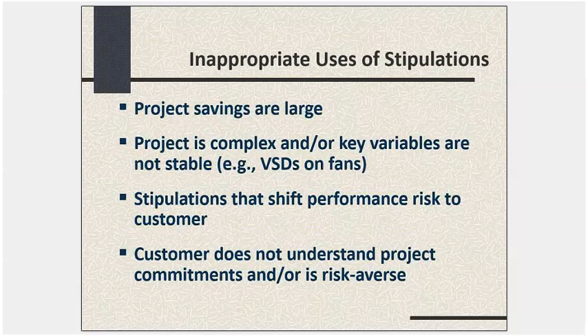Now, when may it not be a good time to use stipulations as opposed to measurements? When the project savings are really big, very valuable. When the project is really complicated, with a lot of variables that aren't stable. You're doing variable speed drives on fans, you really want to know if it's controlling a big fan motor, you want to know how that VSD is performing, you don't want to be guessing about it. A stipulation that shifts a huge amount of performance risk to the customer could be an issue depending on the particular ECM. Or if the customer doesn't understand the project commitments and is really risk averse and says, I know it might be cheaper to stipulate this value, but I want to go ahead and measure it, and I'm willing to spend the money. That's how you get your M&V budget up to $600,000 a year.